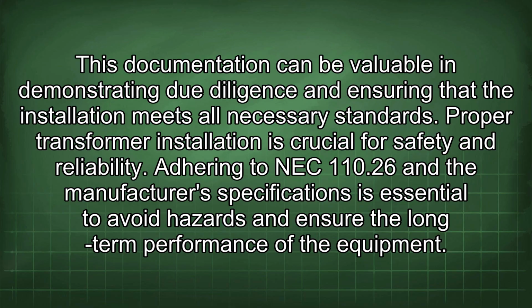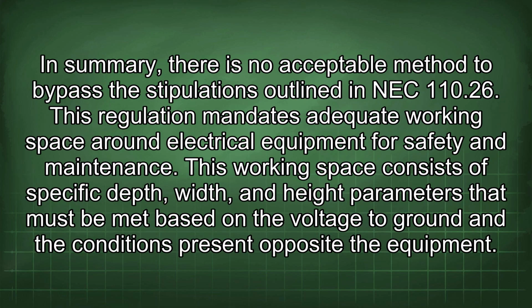Adhering to NEC 110.26 and the manufacturer's specifications is essential to avoid hazards and ensure the long-term performance of the equipment. In summary, there is no acceptable method to bypass the stipulations outlined in NEC 110.26. This regulation mandates adequate working space around electrical equipment for safety and maintenance. This working space consists of specific depth, width, and height parameters that must be met based on the voltage to ground and the conditions present opposite the equipment.